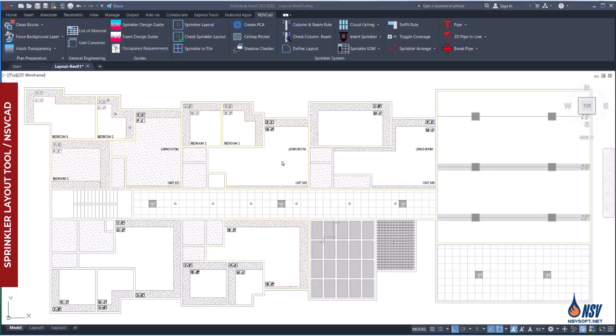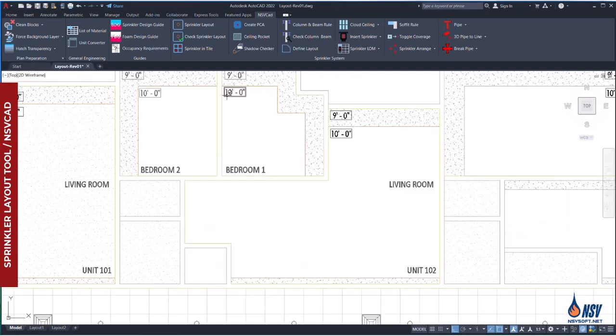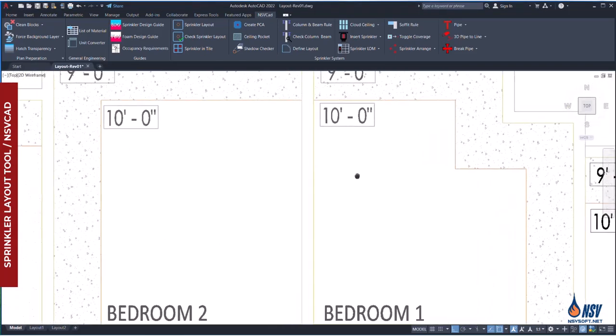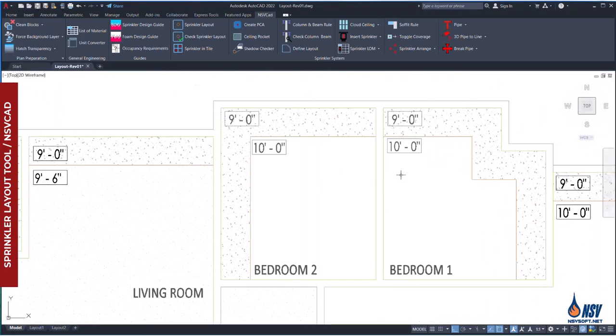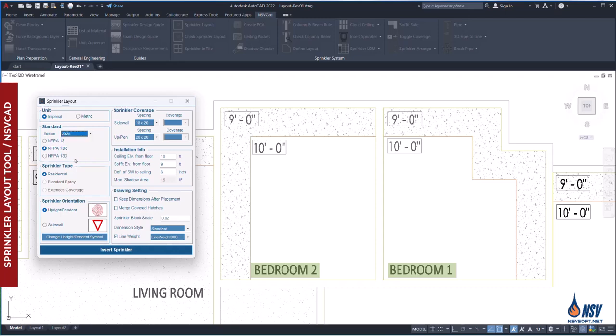In this section, we'll explore how NSV CAD can assist in applying ceiling pocket requirements during sprinkler system design. We'll locate residential sprinklers in bedrooms 1 and 2 in accordance with the 2025 edition of NFPA 13R. Since these rooms do not have suspended ceilings, sidewall sprinklers will be used.